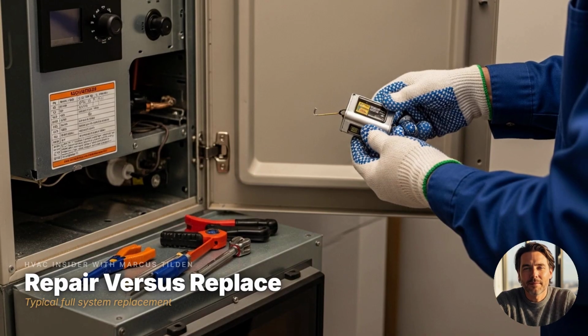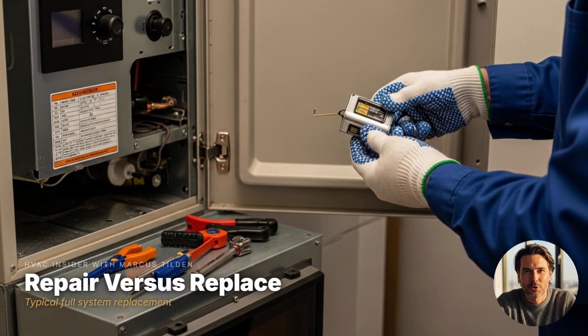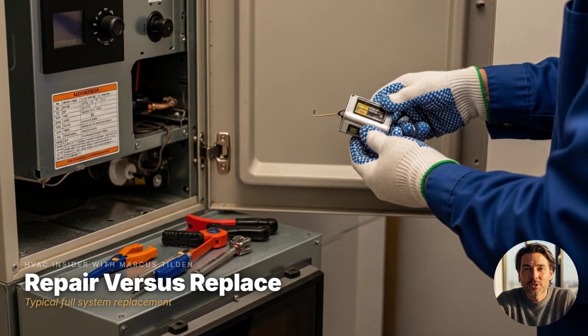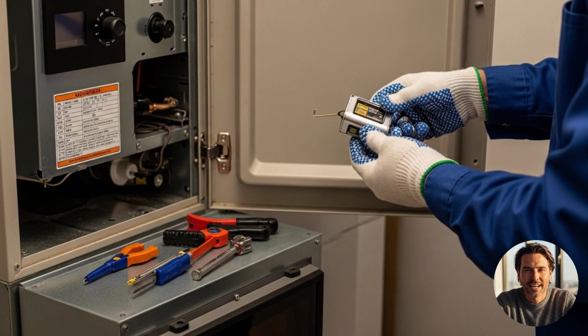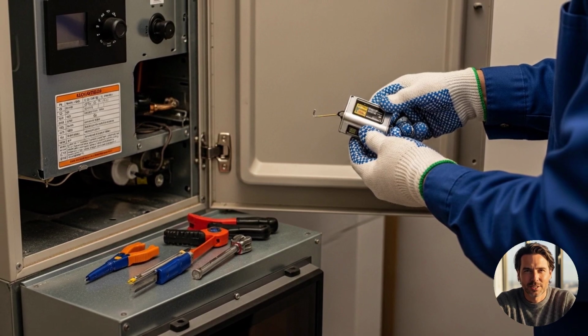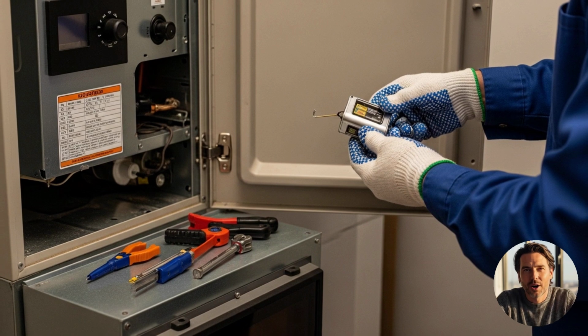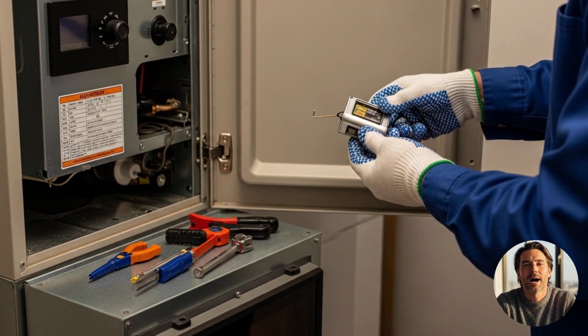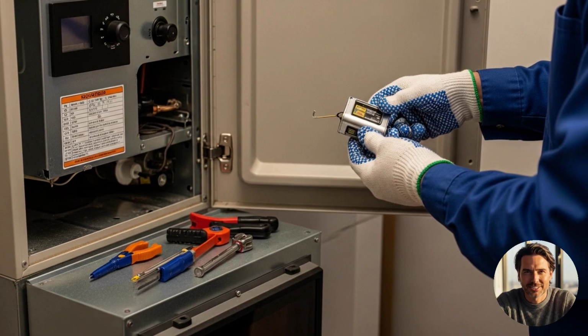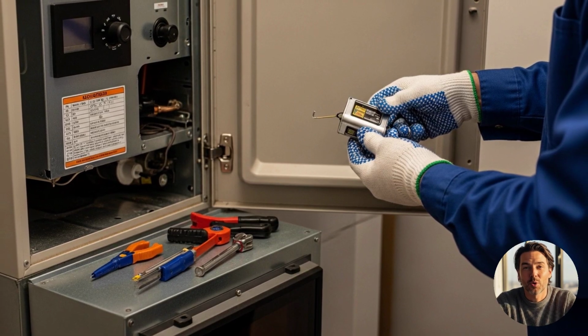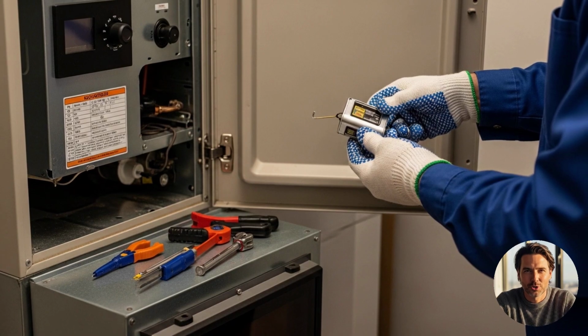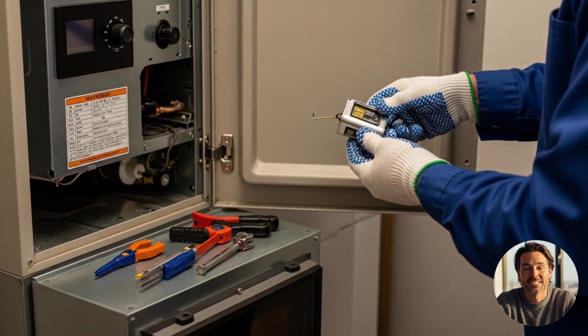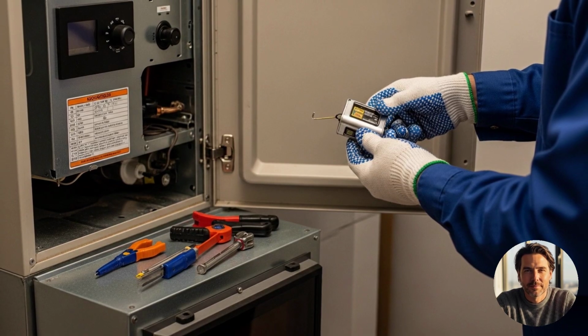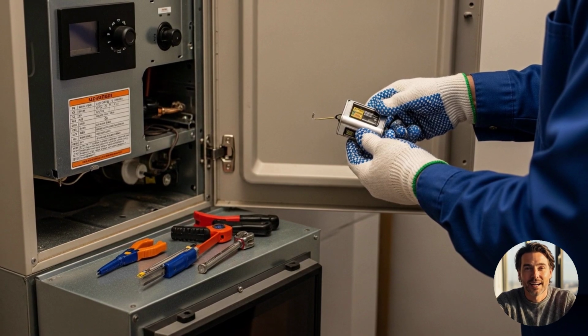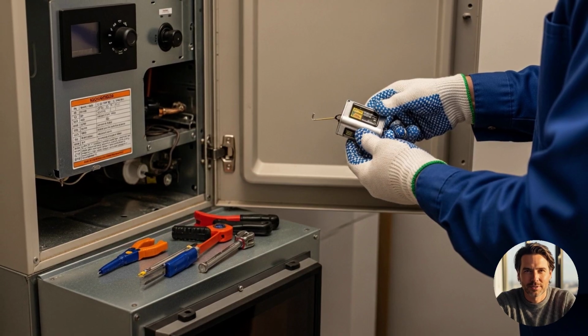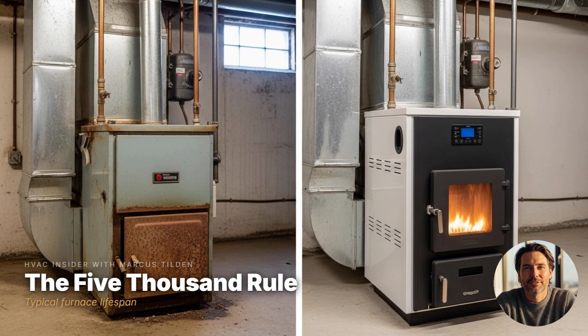Here comes the big one: replace the whole system instead of repairing it. This is where the real money lives. A full high-efficiency replacement commonly lands somewhere around $6,000 to $12,000 or more. Meanwhile, a lot of failures are a $200 capacitor, a contactor, or a control board. When a tech walks in for a no-heat call and walks out trying to sell you a complete system, slow everything down. Ask what specific part failed and what that single repair would cost on its own. You need a way to decide, not a feeling.